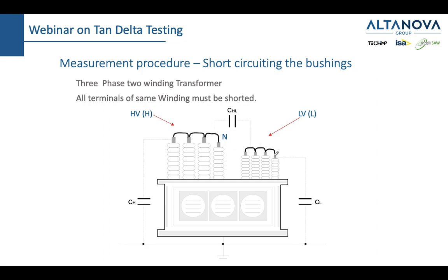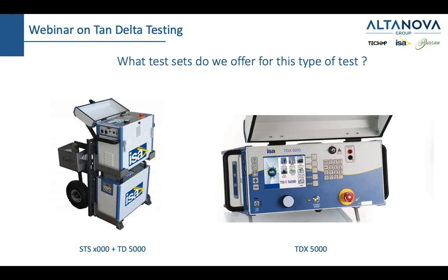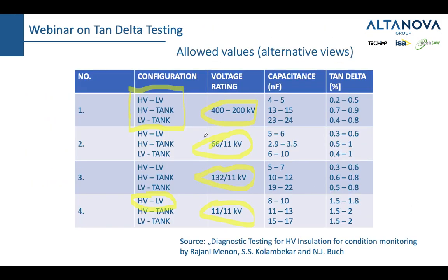And for this example, we are taking a transformer which has a primary and a secondary side. And as you do this, you create a situation where you have, as we spoke before, three capacitors. You have the capacitance between the high voltage and the low voltage, and the capacitance between the high voltage and ground, and low voltage and ground. The standardized names are CHL, for high voltage to low voltage, CH, and CL. You can see that that's how this table was made. This is CHL, this is CH, and this is CL.